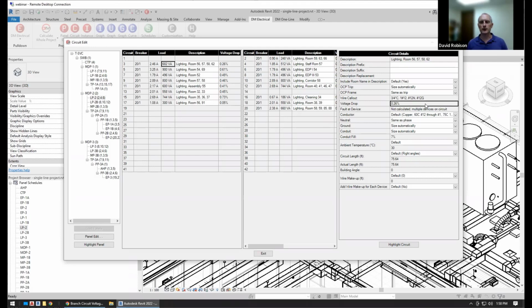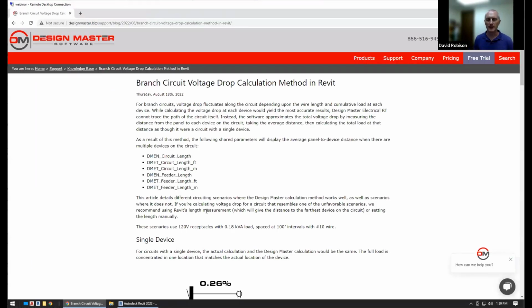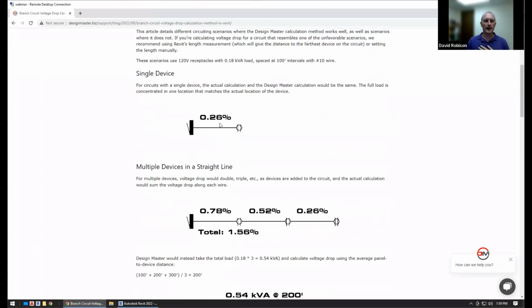For voltage drop, if you have a single device, it works out because the one device is all that's there. And so the length to that device is the entire length. It does get a little bit tricky when you have multiple devices on your circuit. We recently released a support article that walks through how this calculation actually ends up working. So I just wanted to take a moment to look at that and walk you through how these calculations end up happening. So for a single device, we've got our panel, we've got our receptacle.